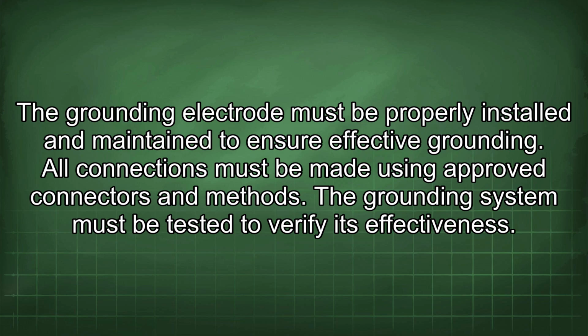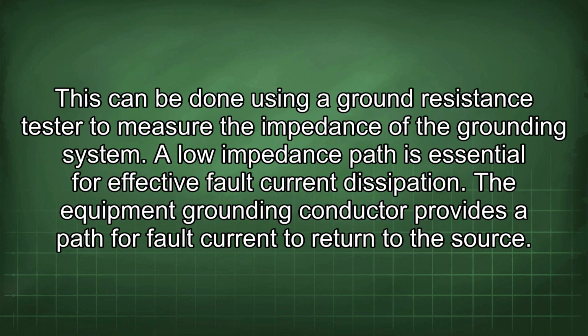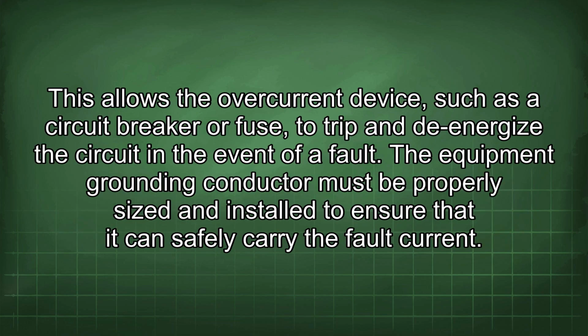All connections must be made using approved connectors and methods. The grounding system must be tested to verify its effectiveness. This can be done using a ground resistance tester to measure the impedance of the grounding system. A low impedance path is essential for effective fault current dissipation. The equipment grounding conductor provides a path for fault current to return to the source. This allows the overcurrent device, such as a circuit breaker or fuse, to trip and de-energize the circuit in the event of a fault.